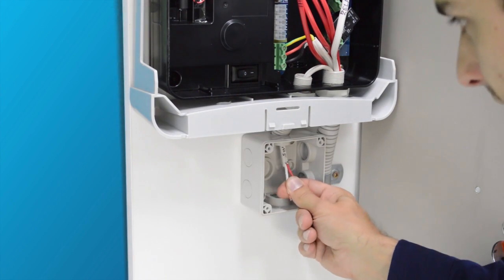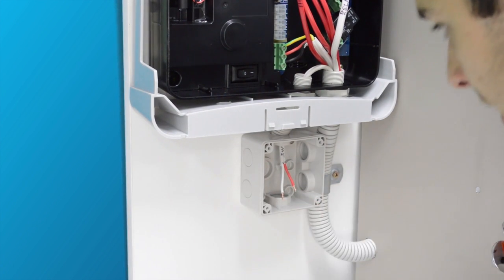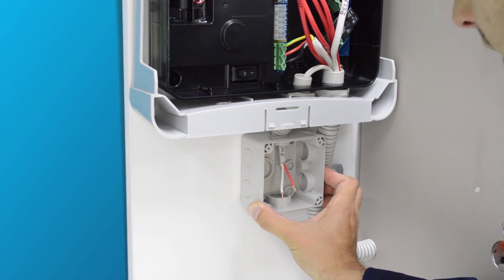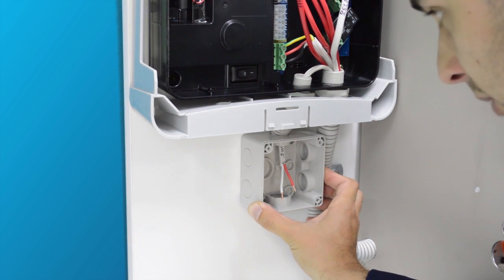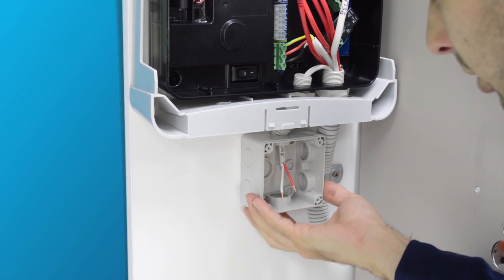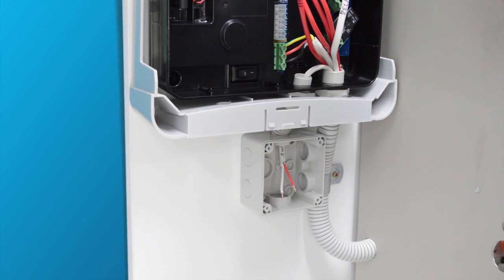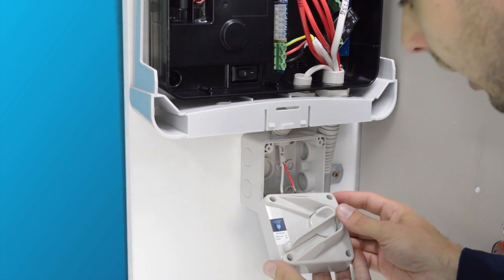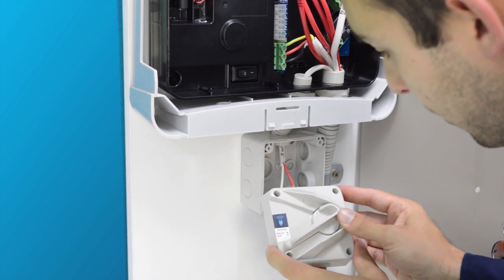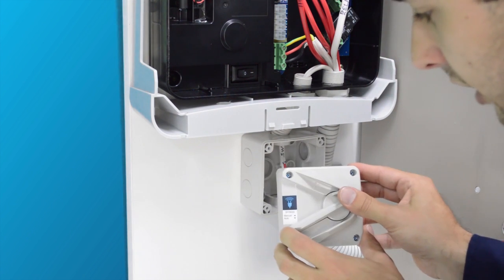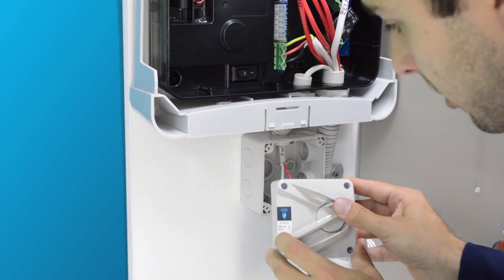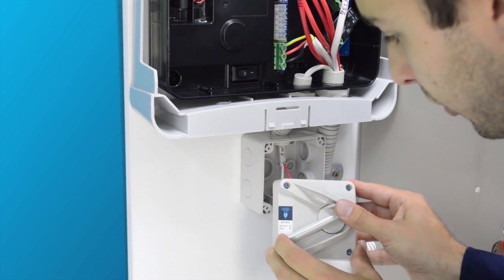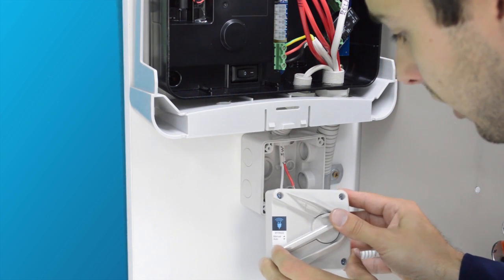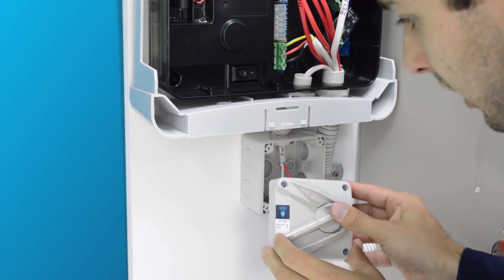Once you've run the twin active down into the weatherproof enclosure, now this may be a weatherproof enclosure that can fit circuit breakers if that's what you're using as a bypass switch. For the training purposes, I'm using a suitably rated weatherproof bypass switch. As you can see, whichever switch you decide to use must be labelled with the bypass switch carbon track sticker and labelled which circuit has been switched.